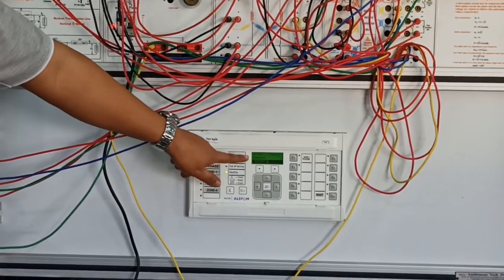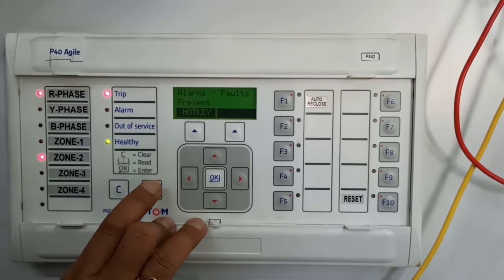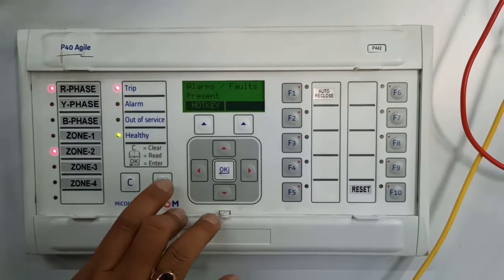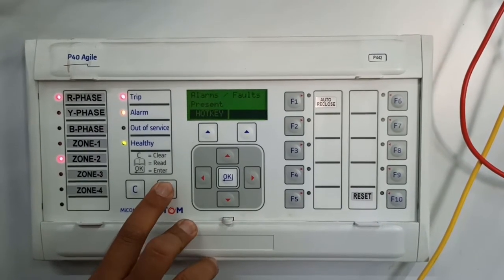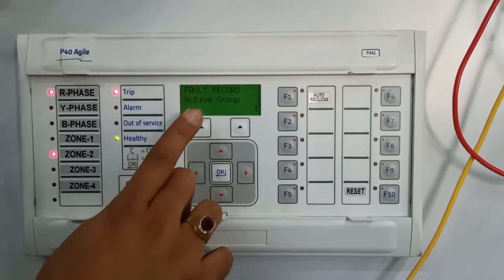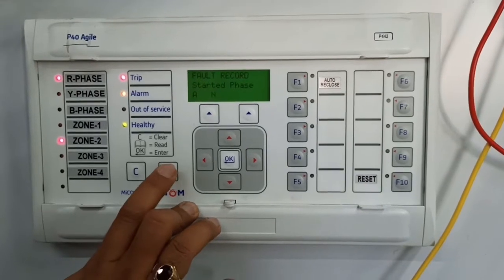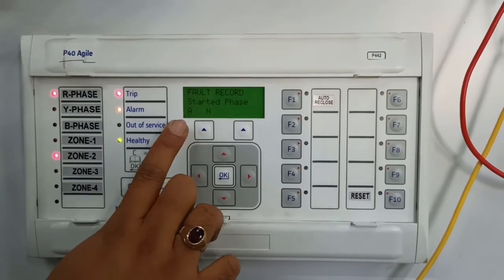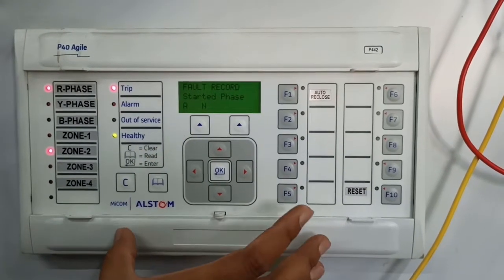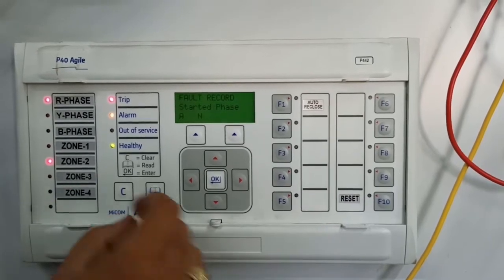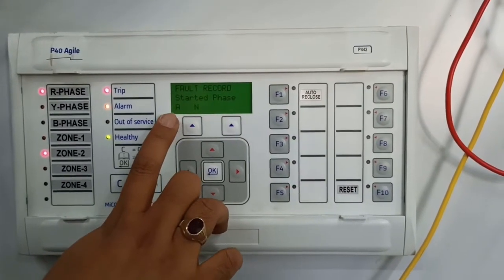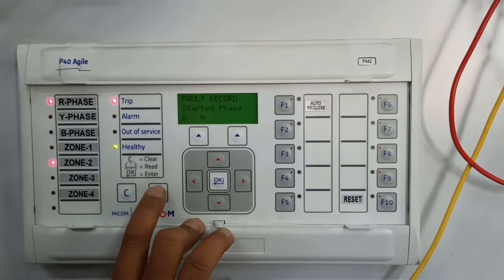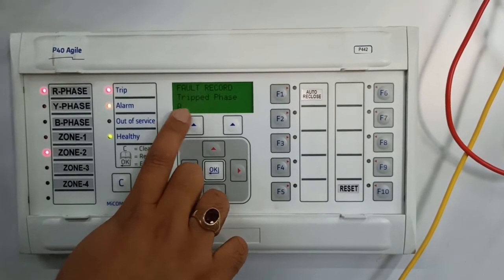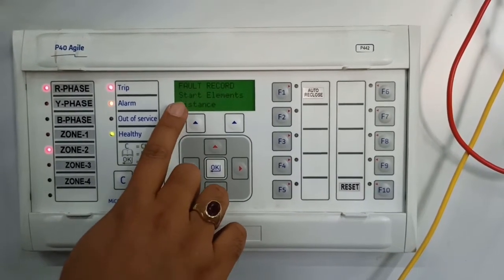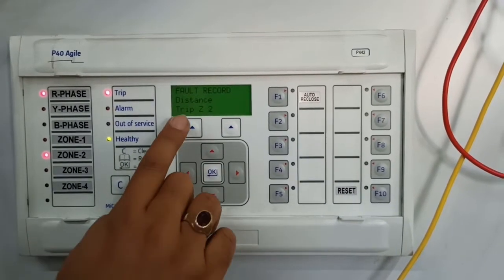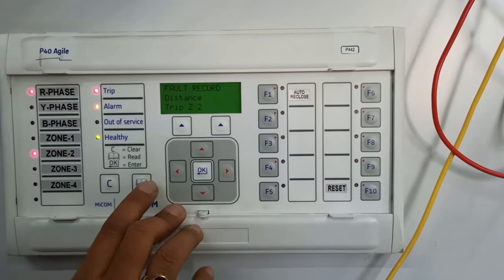From this display we can check the record of the fault. In order to read the fault, you have to press the book key here. It shows fault record active group 1. If you press it again, it shows started phase AN. A is nothing but R, since for this relay the phases are given as ABC. So AN means R phase to neutral. Then phase A is trip, start element distance. The trip is in zone 2. Here it is shown as zone 2.